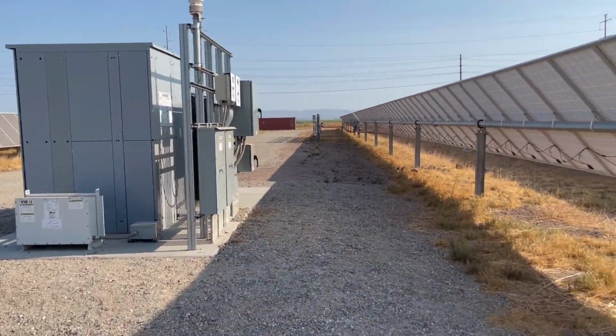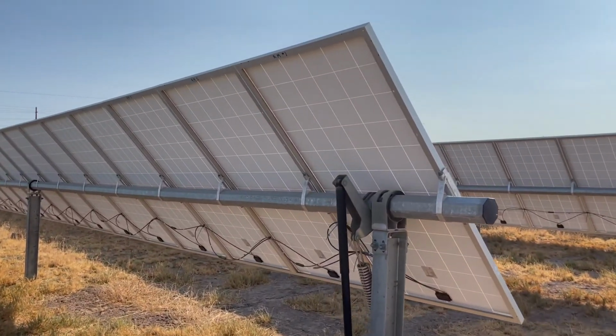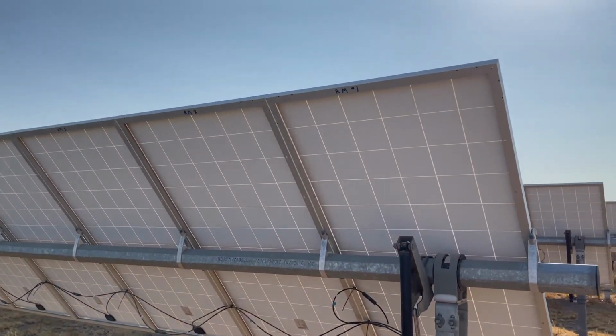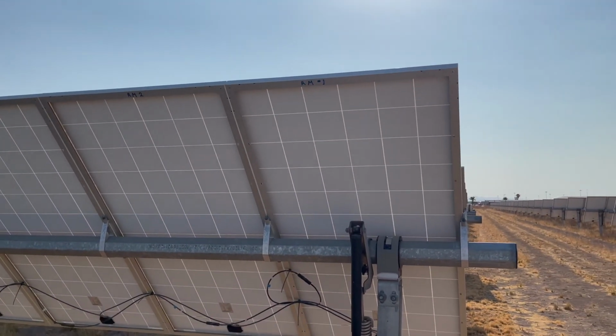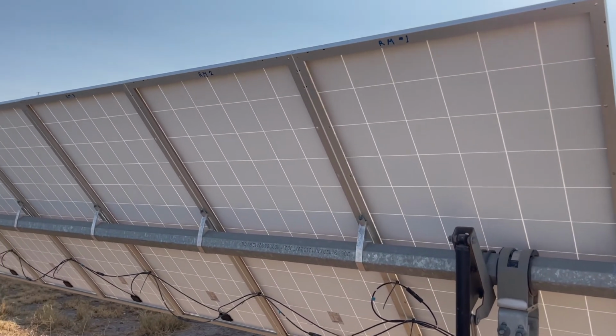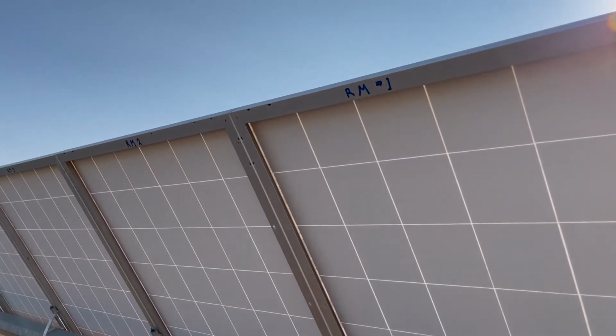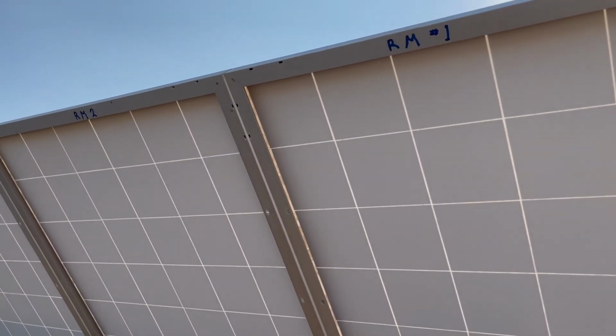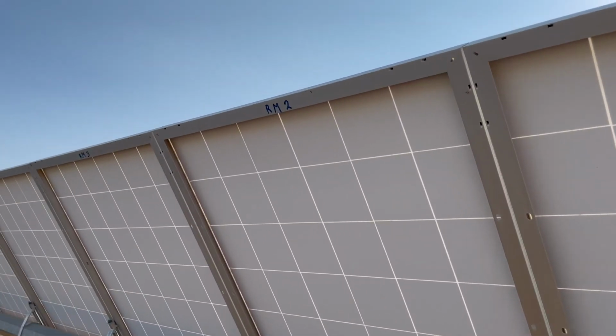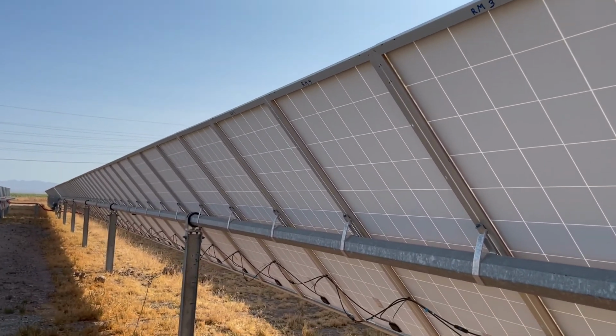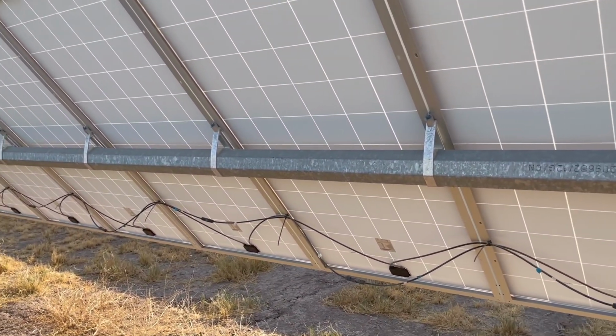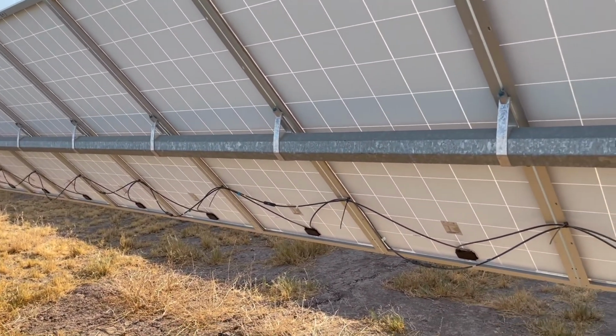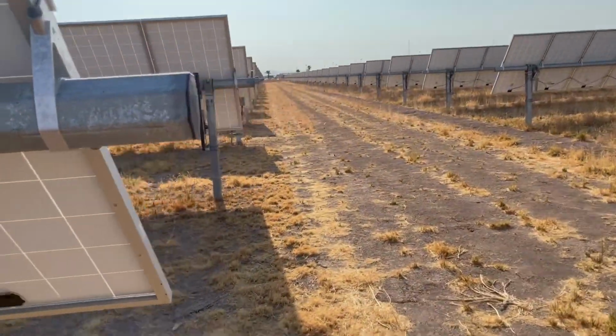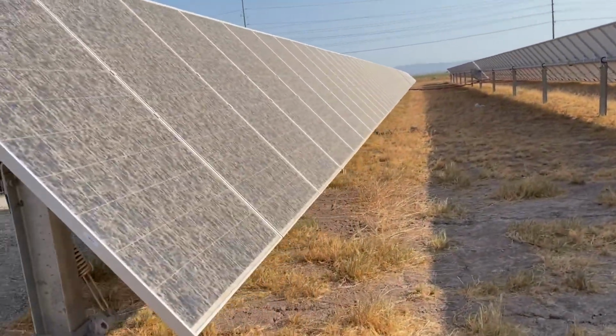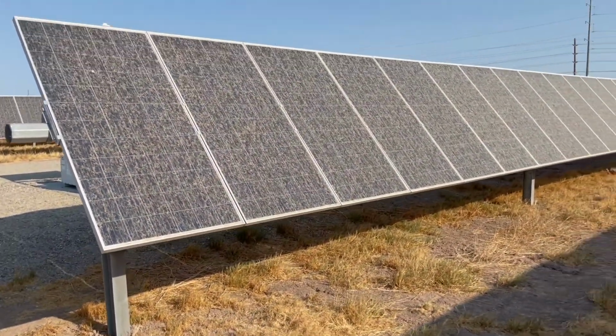Interesting. And continuing the soiling testing, here's pad number 1, transformer pad number 1. And right here, the closest set of modules are the designated reference modules. You can see the marking there on the frame, RM, so reference module RM1, 2, 3, 4, 5. This is what I tested just a few months ago at the annual inspection, where I washed them, tested them and washed them. So strangely enough, they look just as dirty.